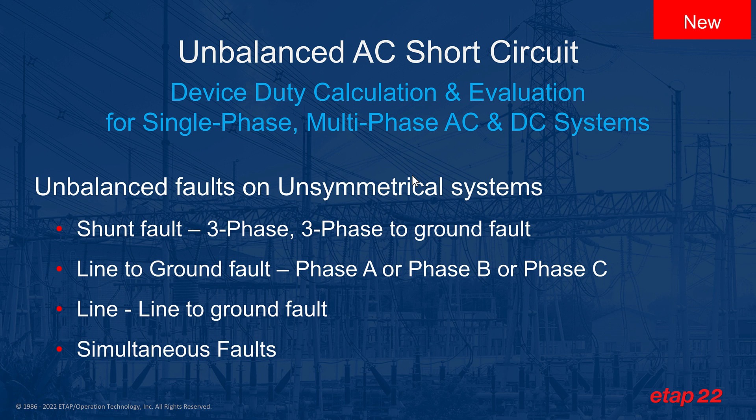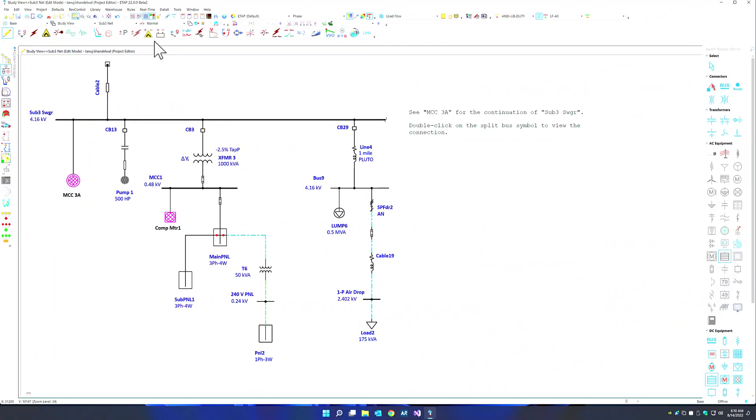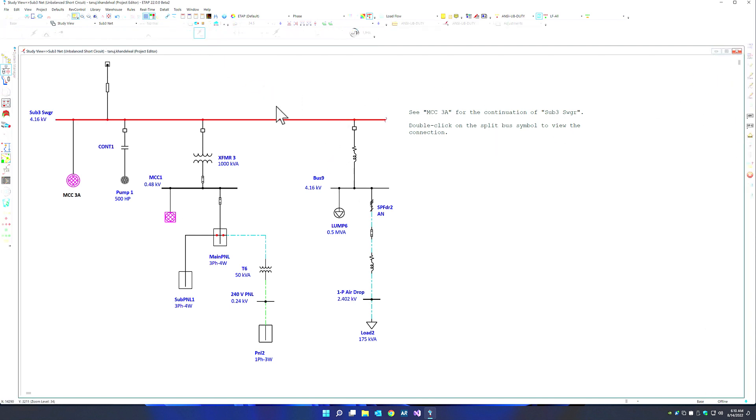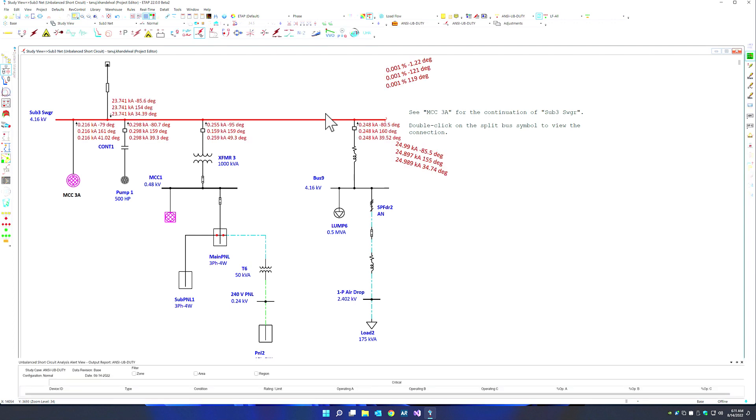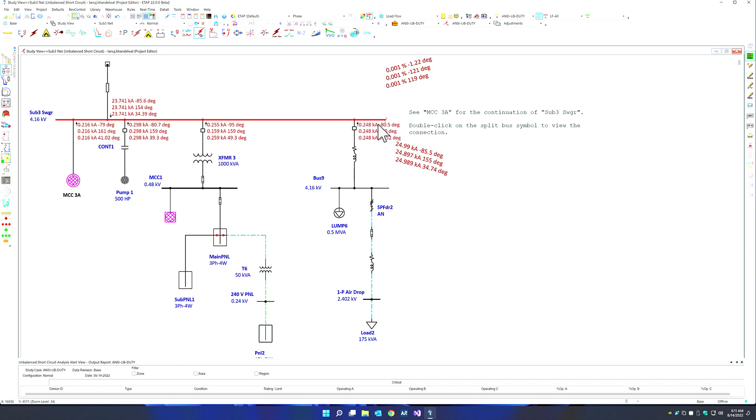So let's see this unbalanced short circuit module very quickly in action. We can simply switch over to our unbalanced short circuit mode and run our simulation. In this case, I'm running a simple device duty simulation. We can see for a combination of a three-phase as well as single-phase system, the individual A, B, and C phase currents and angles, as well as the contribution from the downstream components.